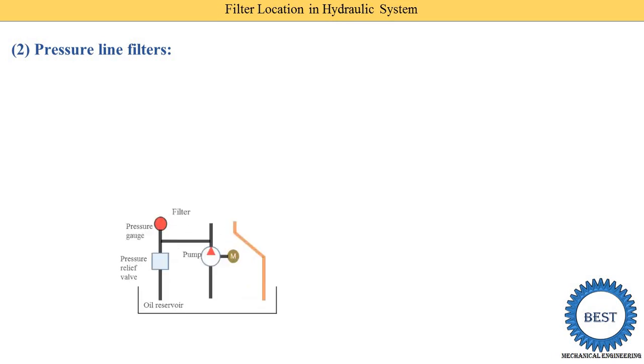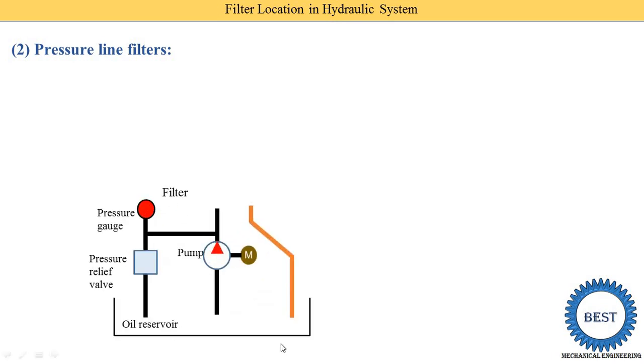The second location is the pressure line filter. In the reservoir the pressure is atmospheric, but pressure line filter means the filter is provided at the outlet side of the pump, where the pressure is higher. Here you can see the oil reservoir, suction pipe, pump driven by a motor, and the outlet of the pump connected with a pressure gauge and relief valve. The filter is provided on the pressure side.